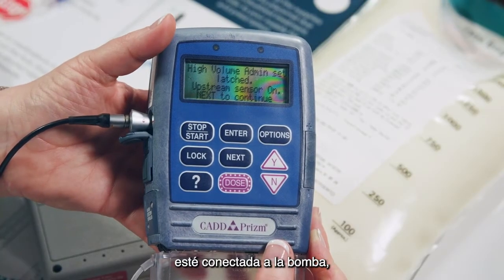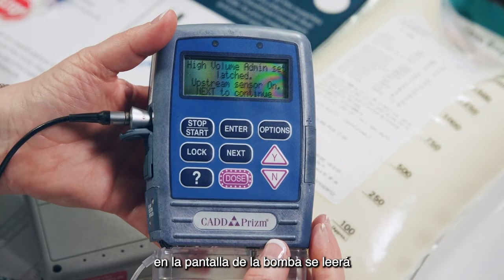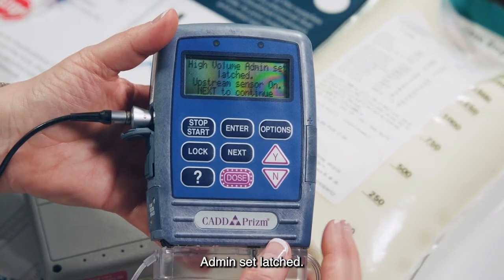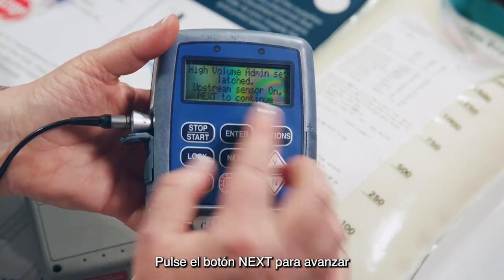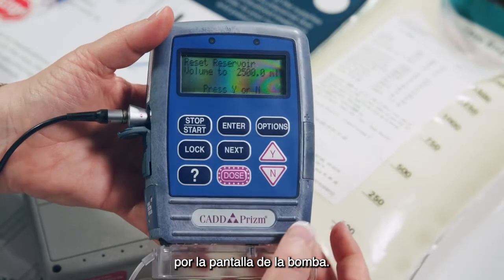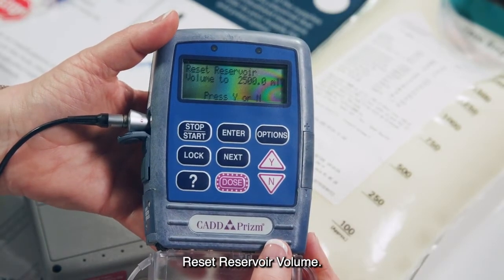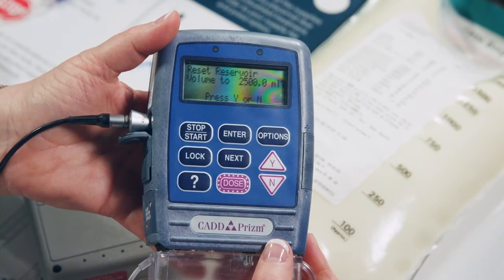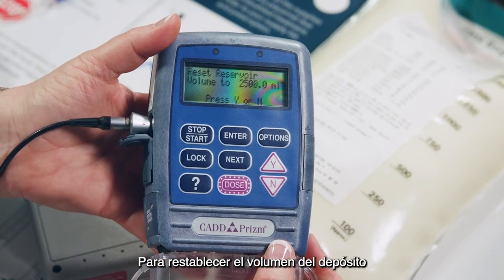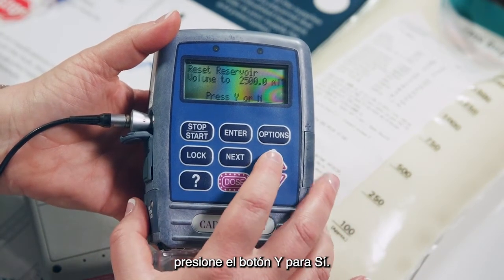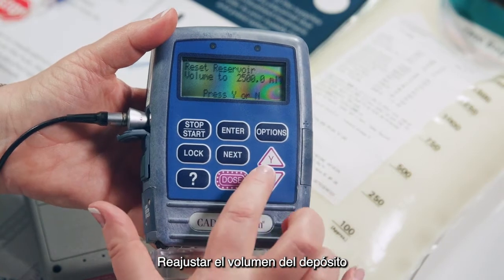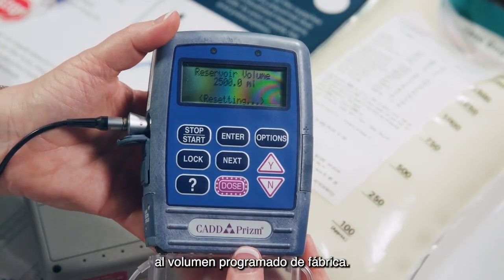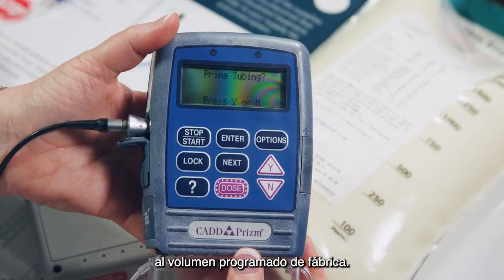Once the cassette is attached to the pump, the display will read Admin Set Latched. Press the next button to advance the pump display. Then the display will read Reset Reservoir Volume. To reset the reservoir volume, press the Y button for yes. Resetting the reservoir volume will change the amount of volume to be infused to the pre-programmed prescribed amount of TPN.